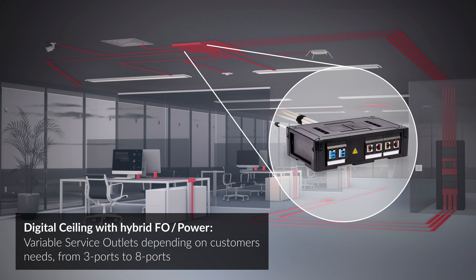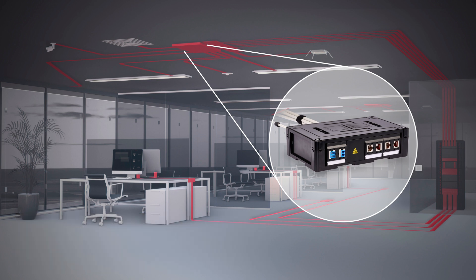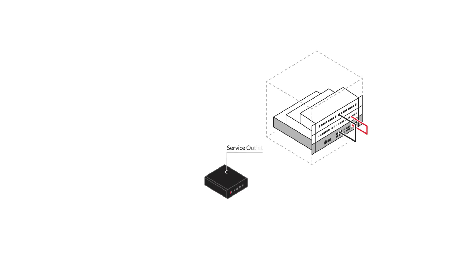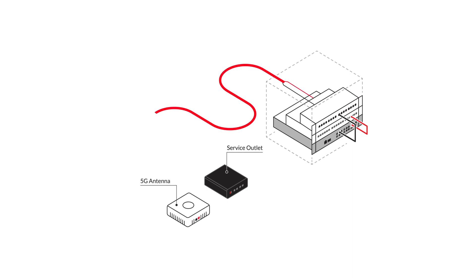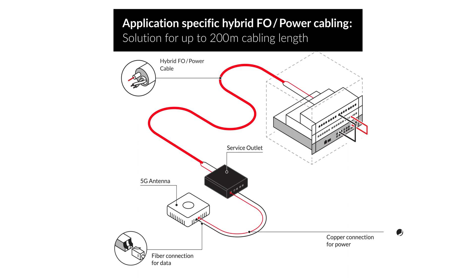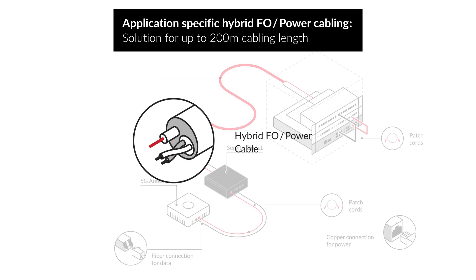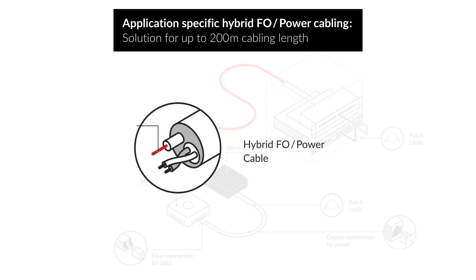To future-proof the solution and provide maximum fail-safe, the minimum requirements can be doubled, resulting in two times LC duplex and four times RJ45 connections. If a digital ceiling with copper LAN cables is not desired or not possible, R&M has developed an application-specific hybrid cable. This hybrid fiber optic and power cable combines a two-fiber single mode round cord with two AWG-16 copper wires under a sturdy outer jacket.